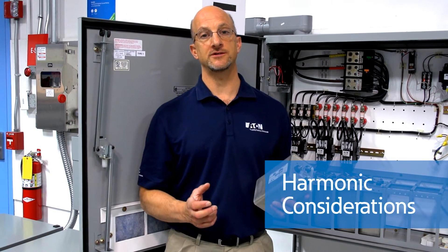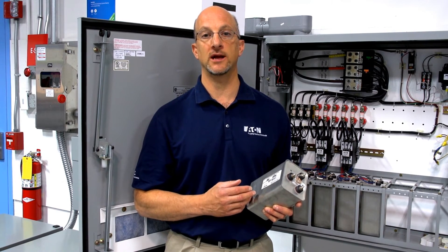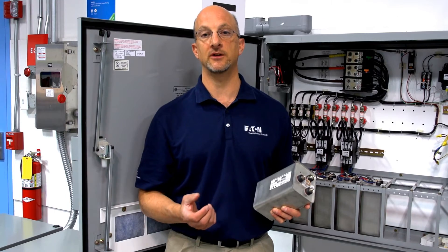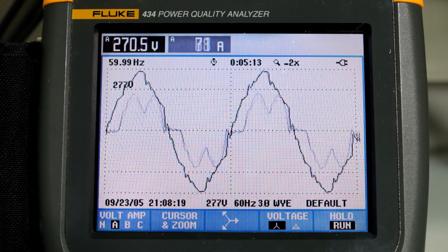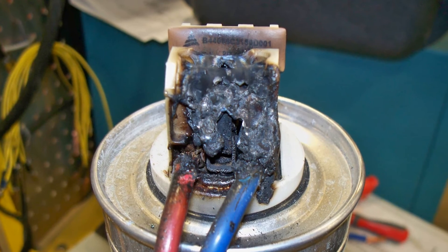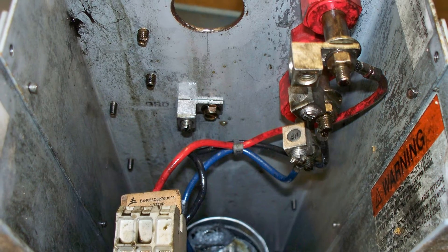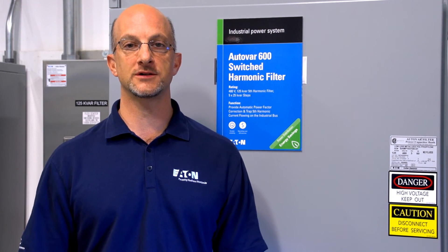Today, harmonics add a whole new dimension to applying capacitor banks. Without careful application, standard capacitors may resonate with the system reactance and may be physically or electrically damaged by this interaction. The Tacoma Narrows Bridge is a classic example of mechanical resonance — the wind kicked the bridge into resonance, and without proper damping, caused it to collapse. An analogous situation occurs with capacitors on a power system: harmonic frequencies, like the wind, can kick the whole system into resonance, causing harmonic frequencies to increase significantly and unfortunately causing equipment to fail. Therefore, if capacitors are applied on a power system with significant harmonics, another method of power factor correction may be required.